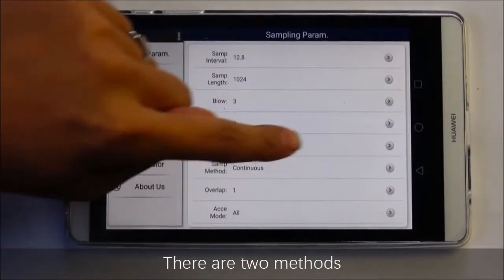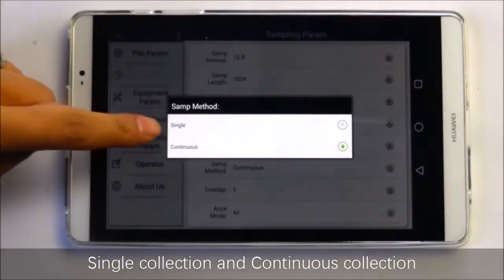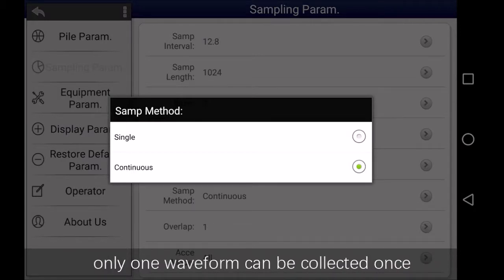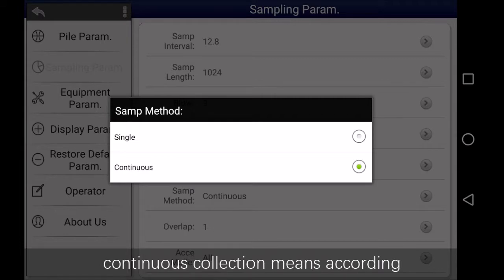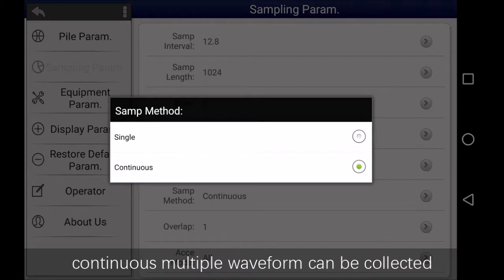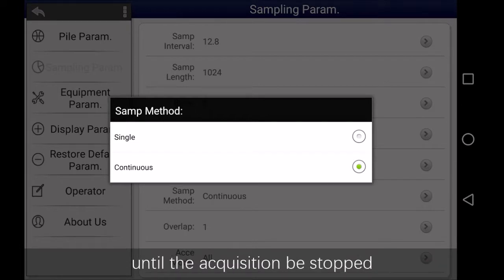Sampling method: There are two methods, single collection and continuous collection. Single collection means, according to the parameter setting, only one waveform can be collected once. Continuous collection means, according to the same parameter set, continuous multiple waveforms can be collected until the acquisition is stopped.